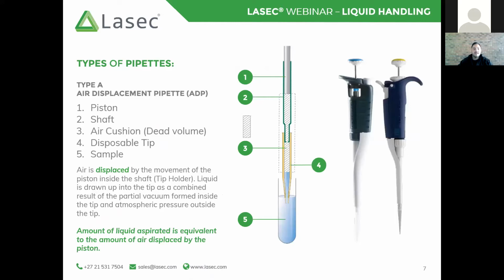All right, so just diving into what an air displacement pipette is. Like the name says, by moving the piston up and down in this pipette, it displaces a certain amount of air. The amount of air that's displaced by the pipette is equivalent to the volume that would then be aspirated. So all of our pipettes have certain common features or constructions. The first being the piston, as you can see illustrated by point number 1 over there. The piston then sits in the shaft of the pipette, also known as the tip holder. The tip is then attached to that tip holder.